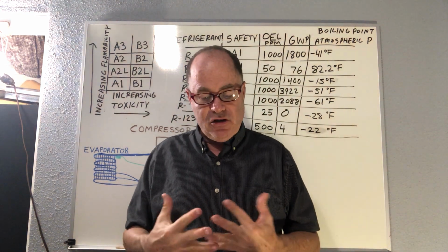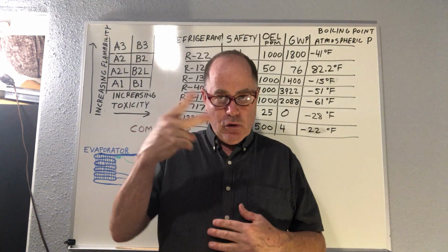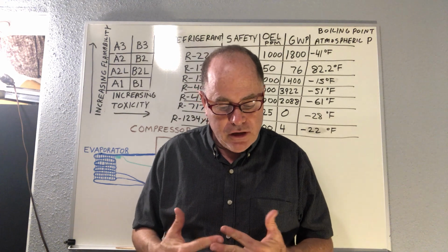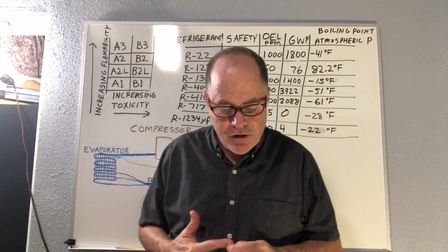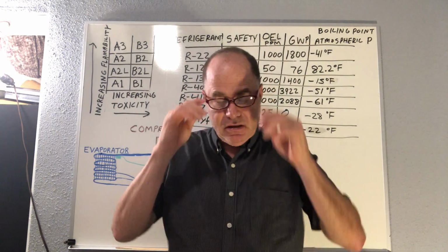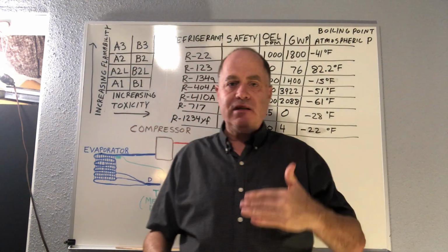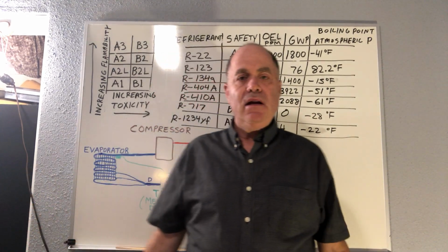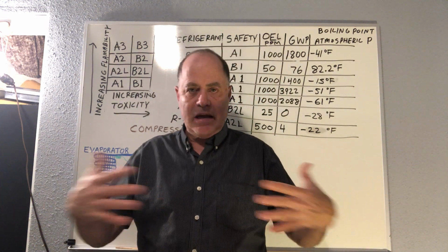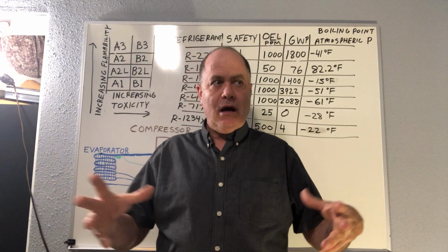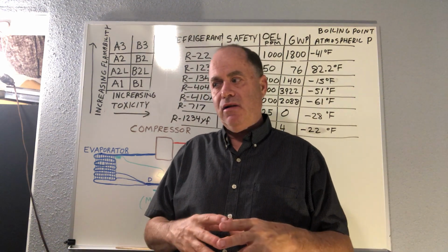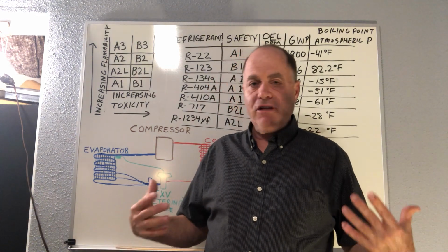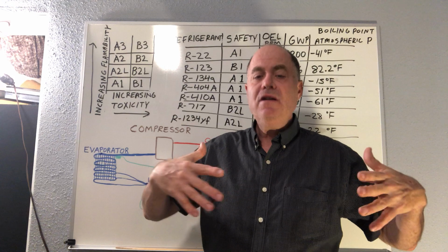Now, the classification of refrigeration systems, the code classifies in two types. Refrigeration systems shall be classified according to the degree of probability that a leak of refrigerant will enter the occupied space. So we have high probability systems and low probability systems. High probability systems means that it can likely get into the space, but then they have some exceptions, like how many parts per million does the volume of the space contain if you had refrigerant released. And generally speaking, it talks about around 6.6 pounds.